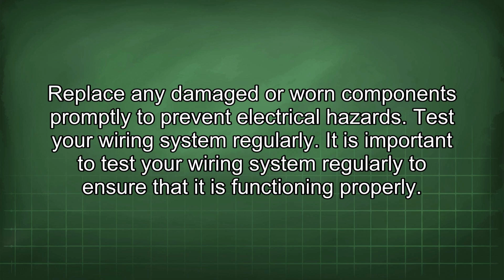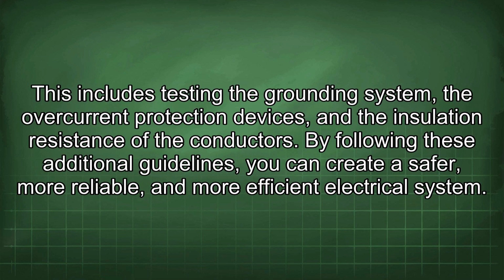Test your wiring system regularly. It is important to test your wiring system regularly to ensure that it is functioning properly. This includes testing the grounding system, the overcurrent protection devices, and the insulation resistance of the conductors. By following these additional guidelines, you can create a safer, more reliable, and more efficient electrical system.